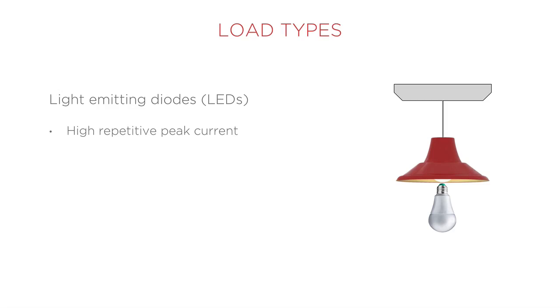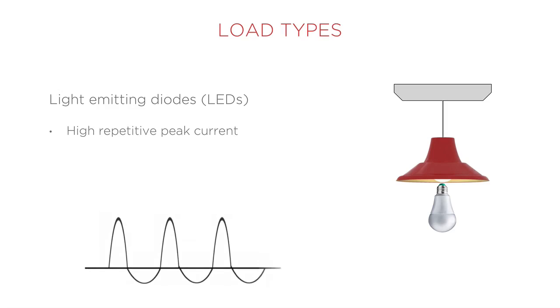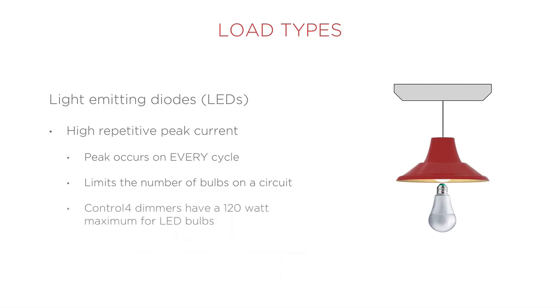LEDs have a high repetitive peak current. It's like the high inrush current, but this time it happens on every cycle, not just when the bulb turns on. This affects the number of LED loads on a single circuit. Too many LED bulbs with high peak currents can trip circuit breakers. Control4 dimmers have a 120-watt maximum for LED bulbs.